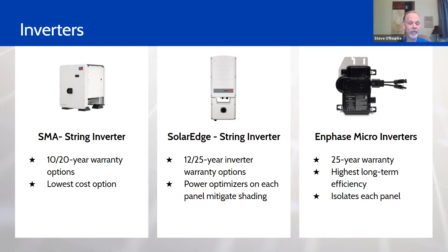Enphase makes microinverters, and this is similar to the optimizing, except it's actually a small inverter on each module. So you're optimizing the production, and you have AC power coming from the module, so you don't have any high voltage DC power coming into a string inverter. They also offer a 25-year warranty on those microinverters. SolarEdge offers a 12-year warranty on the string inverter and a 25-year warranty on the optimizers, and you can also get an extended warranty for the inverters.